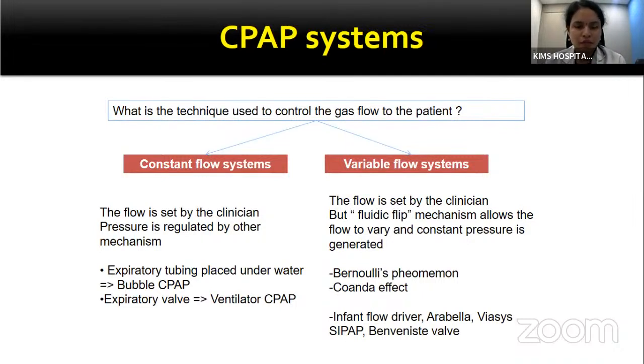Now that we are convinced and we have enough evidence for the use of CPAP in extremely preterm neonates, what are the different types of CPAP delivery systems and which one is more advantageous? So broadly, based on the type of gas flow that is used in CPAP systems, you can divide them into constant flow or variable flow systems. In constant flow CPAP systems, the flow is set by the clinician at a constant number, and the pressure is a function of the resistance that is being offered, either in the form of an underwater seal in the underwater bubble CPAP system, or it could be offered by an expiratory valve in ventilator CPAP.